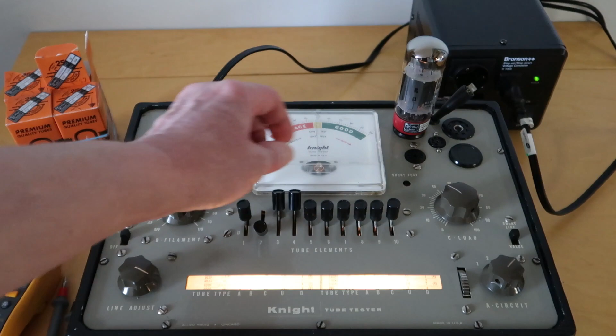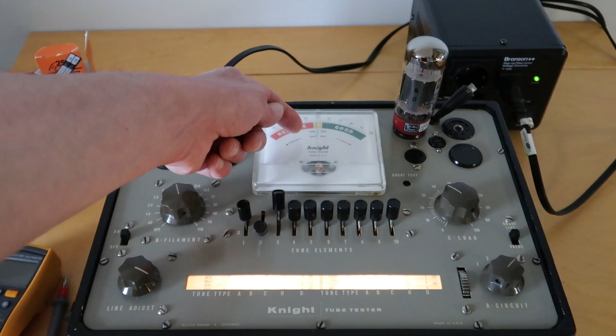Now, I really don't know how it measures this, by the way. How does it measure whether there's a vacuum in there? Because you've no direct access to the inside of that glass envelope. However, the test is for this to go down one position, all detailed in the roll chart, and then to actuate the test and watch the meter fall into the good area on the gas test, as you can see by the meter. Okay? It passes its gas test, whatever that means.